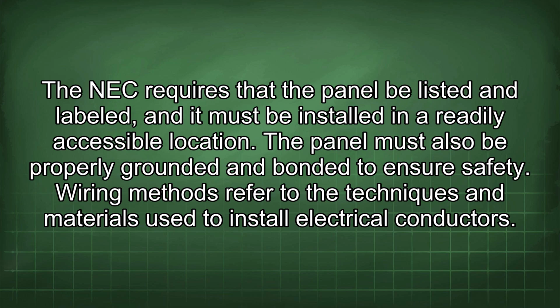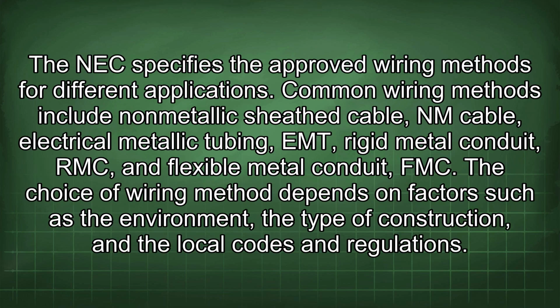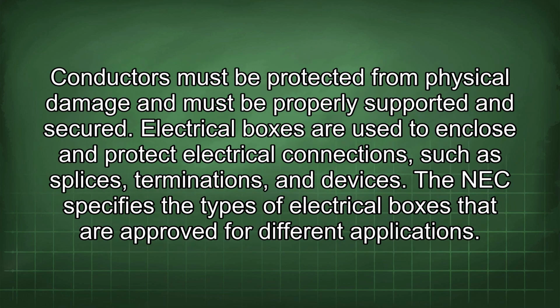Wiring methods refer to the techniques and materials used to install electrical conductors. The NEC specifies the approved wiring methods for different applications. Common wiring methods include non-metallic sheath cable, NM cable, electrical metallic tubing, EMT, rigid metal conduit, RMC, and flexible metal conduit, FMC. The choice of wiring method depends on factors such as the environment, the type of construction, and the local codes and regulations. Conductors must be protected from physical damage and must be properly supported and secured.